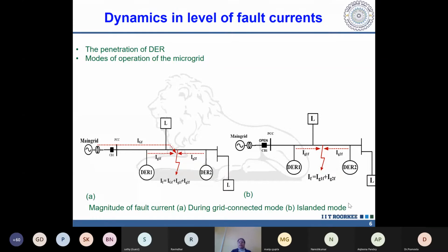Even in islanded mode, let's say DER2 is switched off due to maintenance, a disturbance, or a fault inside its components. If DER2 is absent, the fault current magnitude changes, and even the angle changes to some extent, depending on the mode of operation of the microgrid. There are two reasons why this dynamics changes.